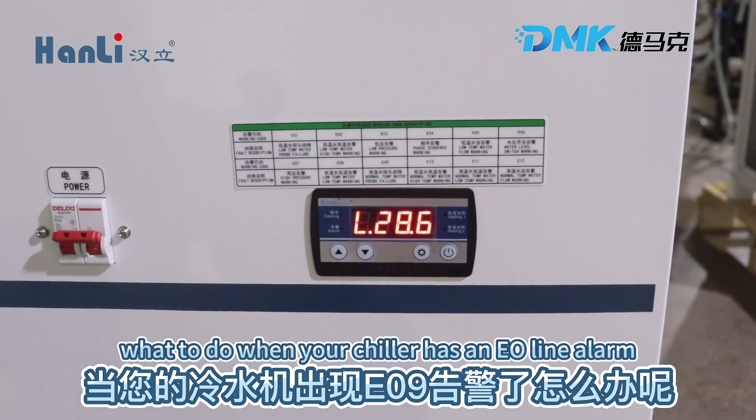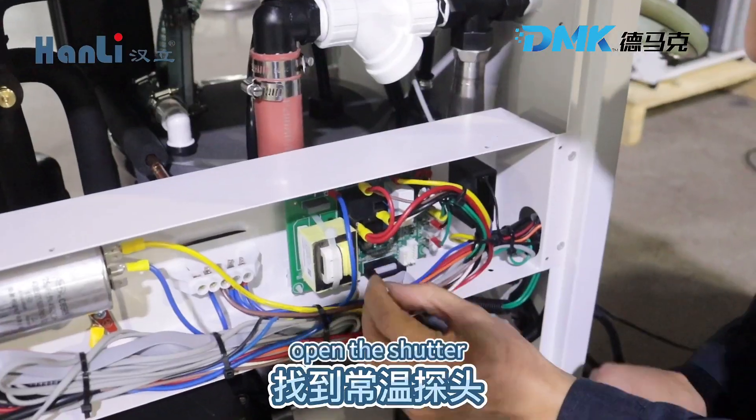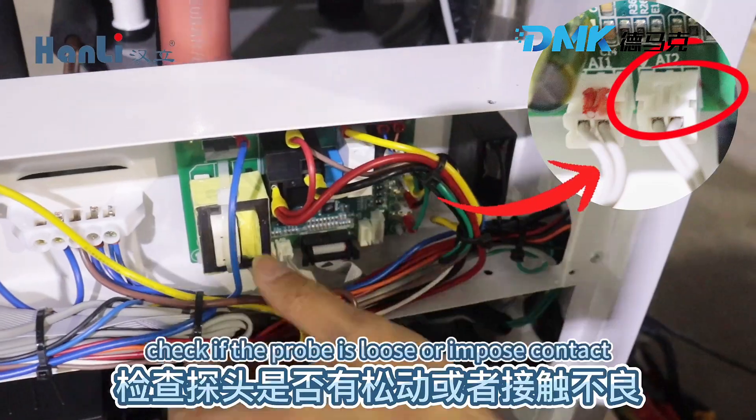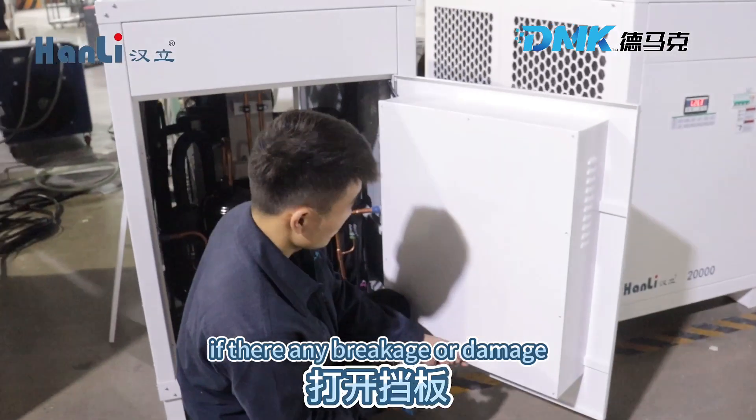What to do when your chiller has an E09 alarm? Must remember to turn off the power. Open the shutter. Find the room temperature probe. Check if the probe is loose or in poor contact. Then check the probe wire for any breakage or damage.